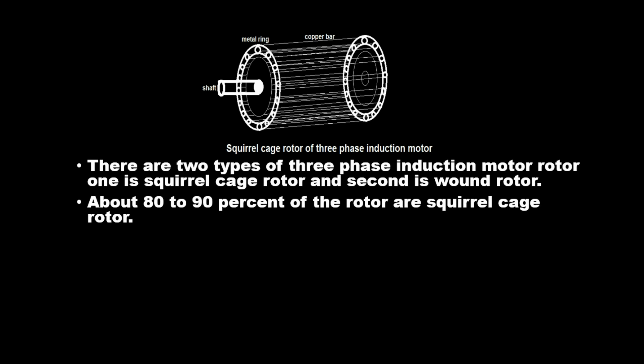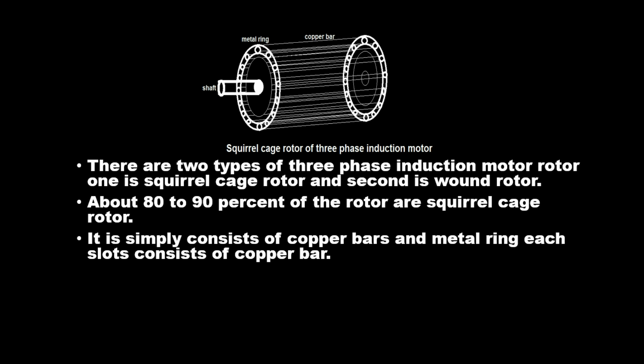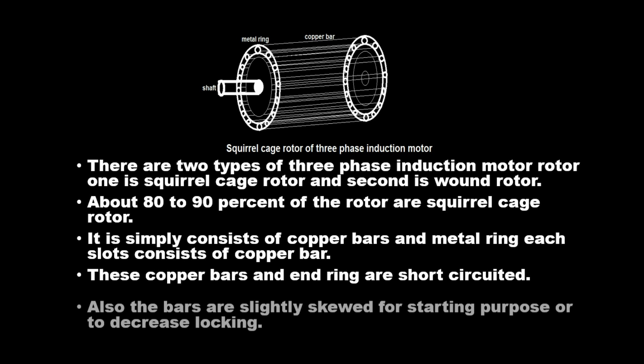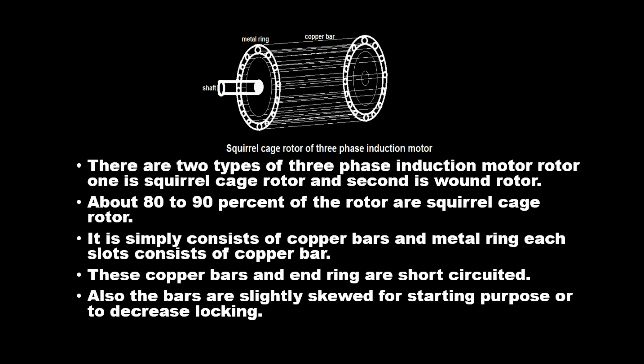About 80 to 90 percent of the rotors are squirrel cage rotor. It simply consists of copper bars and metal ring; each slot consists of copper bar. These copper bars and end ring are short-circuited. Also the bars are slightly skewed for starting purpose or to decrease locking.